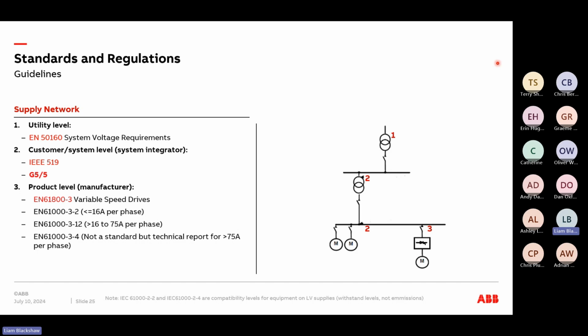The ones you probably get involved in a lot are the second set, which is at the customer or system level. If we're looking at it from a UK perspective, we're looking at G55, which came into effect around June 2020, so just over 4 years ago, where the prominent changes were things like how we assess this, the various stages, and the extension of harmonic orders up to the 100th order as well. You also have, and this is more if you're a manufacturer, the product level harmonics. So you've got the 61800s or the 61000s, depending on the loading of that piece of product, at least anyway.